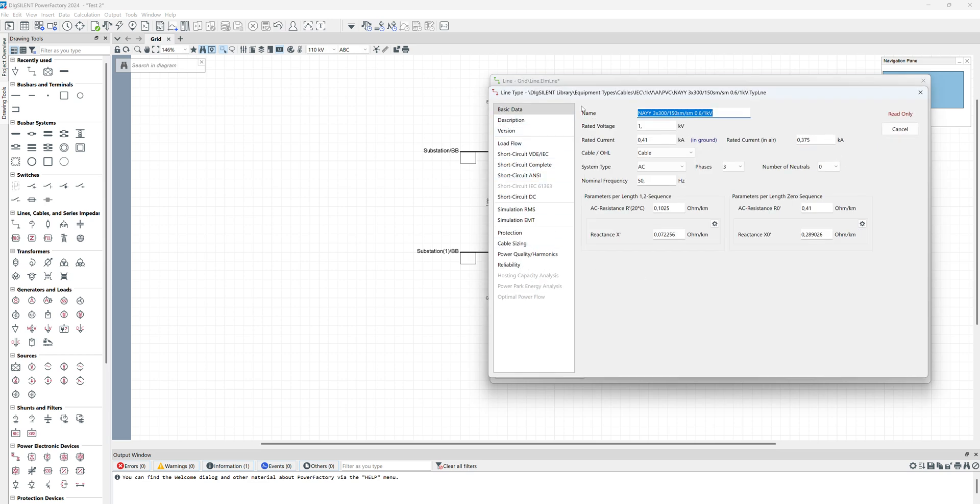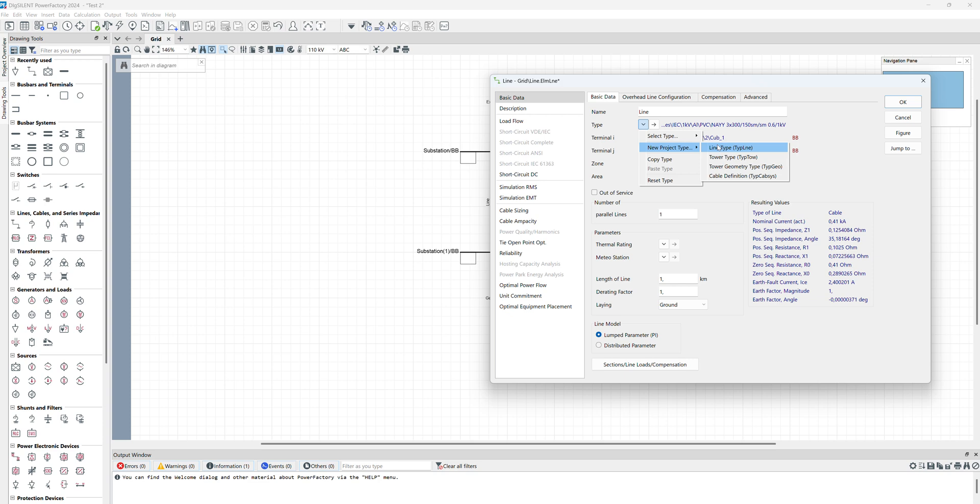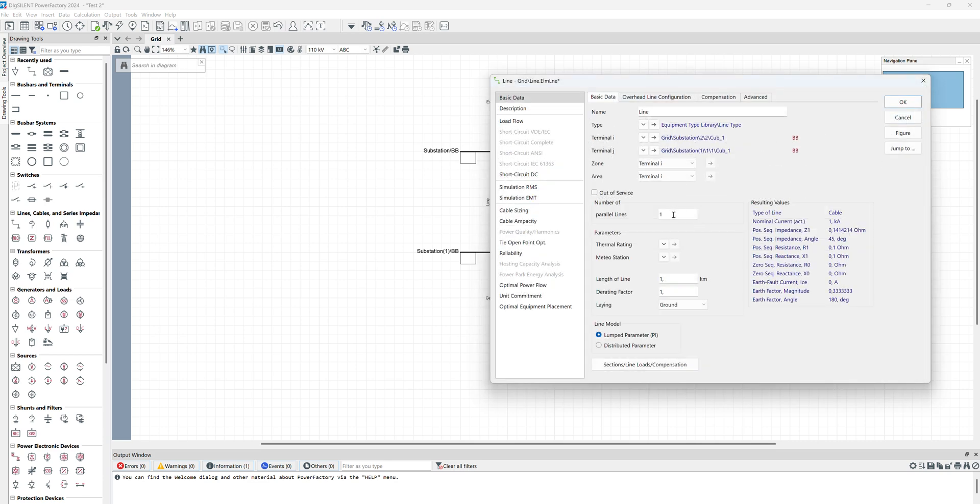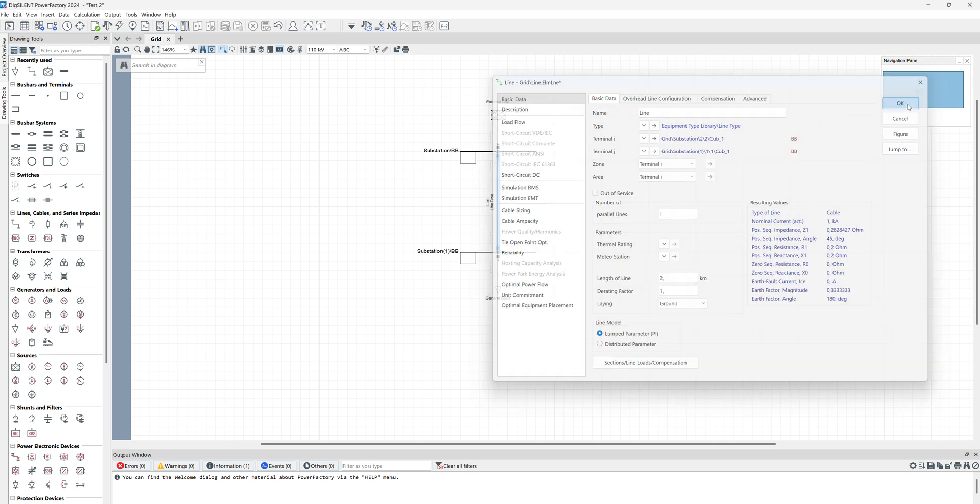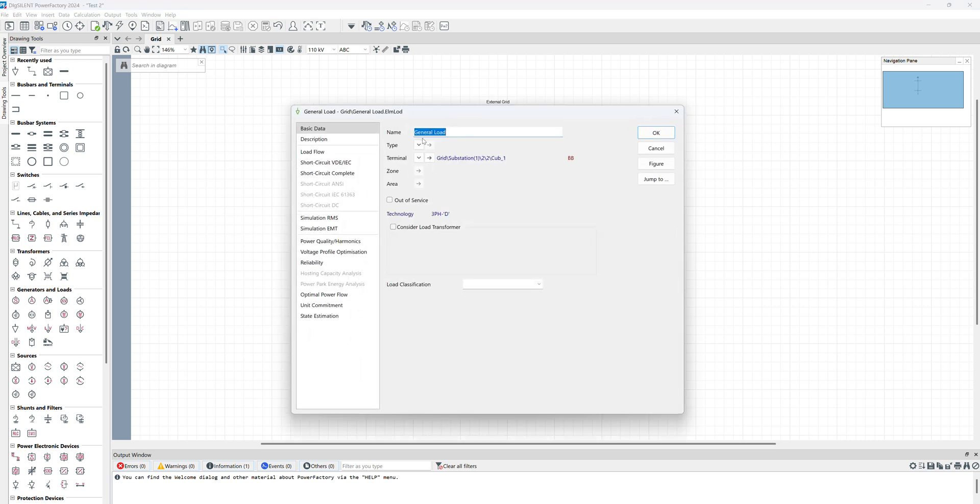If I click for example on this one, click OK, it's allocated here. If we click on the second arrow you can see this specification - it is from some real cables. But if you want to define the line based on your specification, New Project and Line Type, and here we had 10 kilovolt - just put it 10 and 0.1, 0.1 for resistance and reactance, and click OK. Then here we have parallel line, length of line, and derating factor and other specifications. Later we will back and discuss about them. Here, for example, we can increase the length of line to 2 kilometers and here we have the automatic calculation for specification of this line.